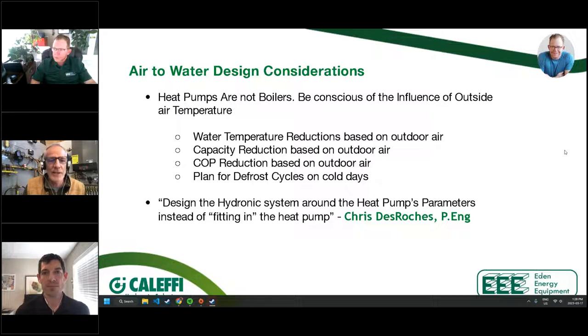So, getting off the heat pump a little bit, just know that it's more about the cycle efficiency than it is the efficiency number on the side of the boiler, whether it's a cast iron or mod con, but we'll talk about that another time maybe. Yeah, well, you make a great point, Bob. I mean, the fact that the appliance is 96%, there's a whole variety of things, like what is the firing rate, what is the return water temperature. There's more in play in the field that impacts that efficiency.